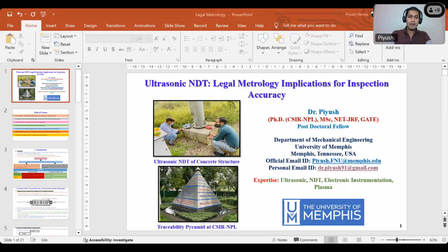The point here is that this ultrasonic pulse velocity is independent of the geometry of the material, but it depends on the elastic properties of the material, like Young's modulus and bulk modulus. So in case of concrete, we can measure this dynamic modulus from velocity, which is a measure of the strength of any material. Now here are a few equations by which we can measure the ultrasonic pulse velocity. Now what is this ultrasonic pulse velocity measurement?